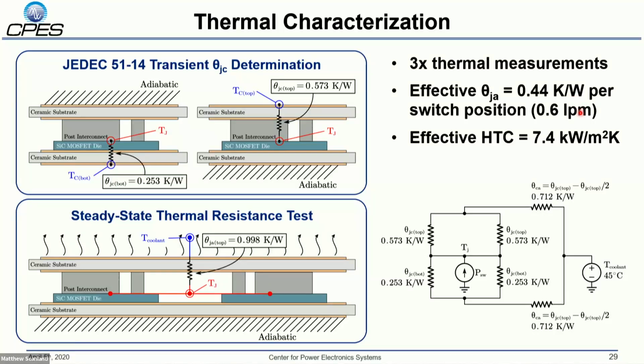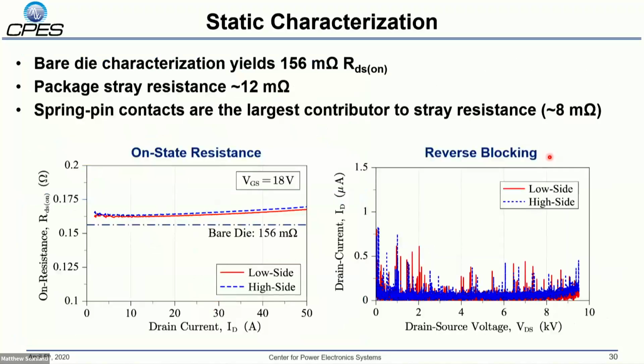That's at a fairly conservative 0.6 liter per minute flow rate. The cooler was designed for a little bit faster than that, but I'm walking it up slowly because I want to see what happens. So we're starting out slow at 0.6 LPM, and as we go on, hopefully we can get this up to 2 LPM. But at that 0.6 liter per minute flow rate, we're at about 7.4 kilowatt per meter squared Kelvin effective HTC.